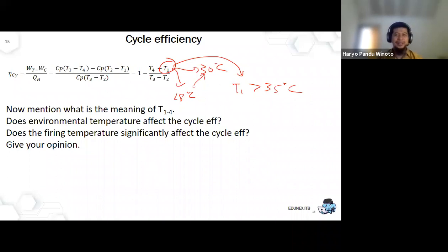they always have the fire truck or the water tank truck ready in front of the gas turbine, and they sprinkle water, so they can get a lower T. That's because you cannot heat it up. You don't want to heat it up that much. Furthermore, when you heat it up, that means what? You increase the flow of fuel. It's also problematic because the overall efficiency will be lower.